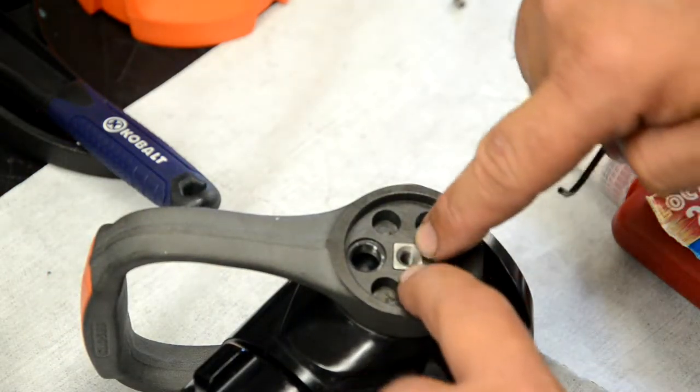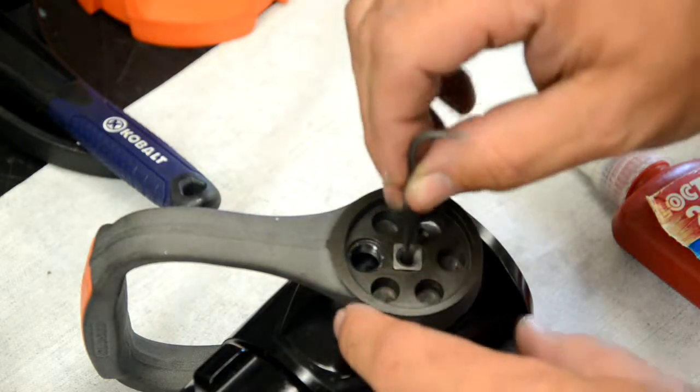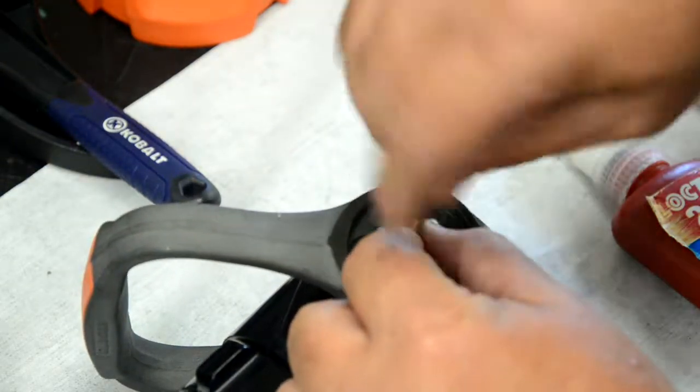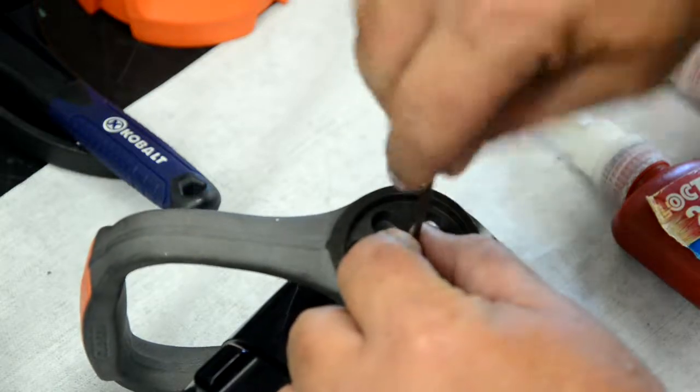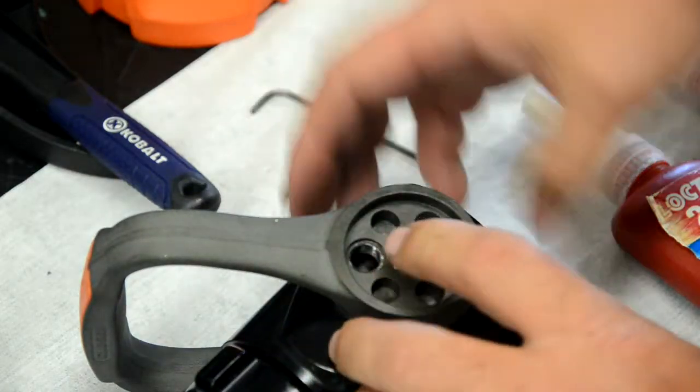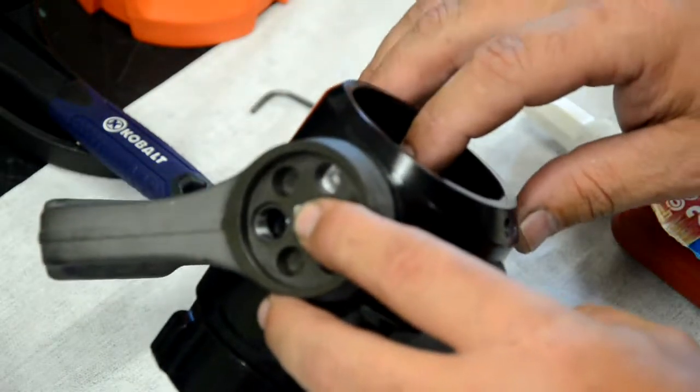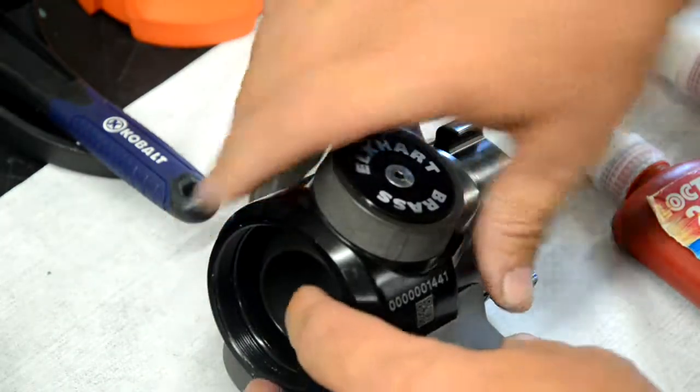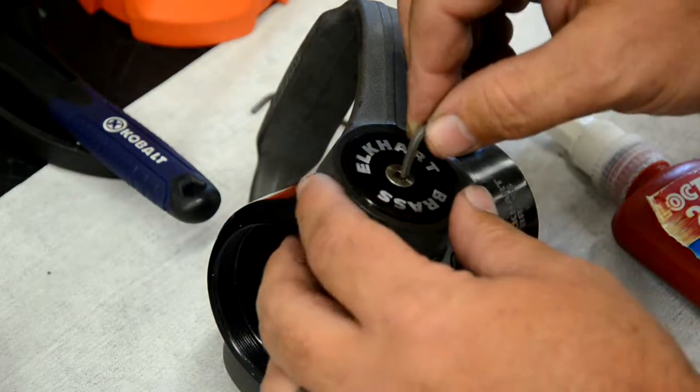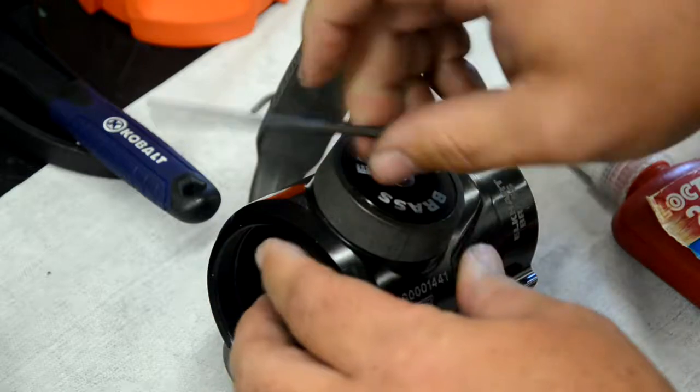Using the small 3/32nds allen wrench, loosen the dog point set screw so that it disengages from the ball valve. Note, the dog point set screw will not back all the way out of the actuator shaft. It's a part of it itself. We're just going to back it out far enough so that it's free from the ball valve. Then, we're going to repeat this process on the other side.